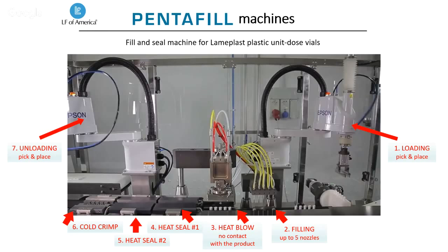Then the next station is the heat blow. We blow hot air to soften the plastic in the seal area. The very important thing here is that the air the machine blows does not come in contact with the solution. The air is blown horizontally, from inside out and from outside of the vial, so there is no contact whatsoever between the hot air and the solution, the product inside the vial. After we blow hot air, the strip goes through one or two heat sealing stations, depending on the capacity and the size of the machine.